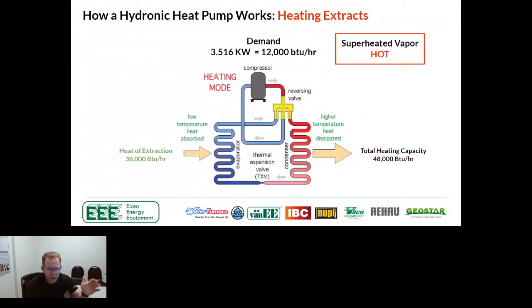So just very briefly going to talk about a hydronic heat pump and how it works. This would be the same whether it's an air to water or a water to water. What we are doing is we are extracting and moving energy when we're in the heating mode. So when you see a COP advertised for a heat pump where it says it has a COP of 3, what that means is for every unit of electricity, we are moving 3 units either from a ground loop in the case of a water-to-water heat pump, or we're drawing that by moving the energy from the air into the space. So heat of extraction is the term that we always use. We are extracting the energy out of the air, or we're extracting the energy out of the water.